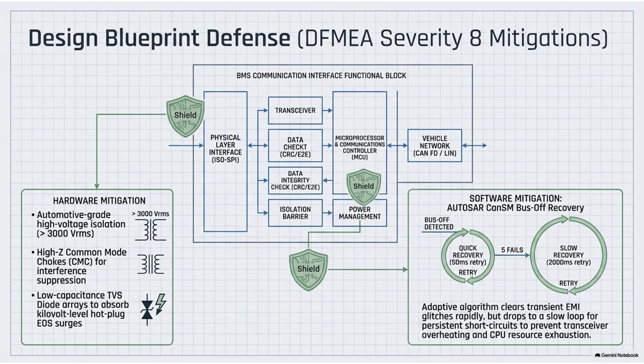What does that achieve? It utilizes the physics of electromagnetism to filter out the noise. Remember how the CAN bus uses differential signals? One wire goes positive, the other goes negative. Because the currents are flowing in opposite directions through the wires wrapped around the donut, the magnetic fields they generate completely cancel each other out. To the differential data signal, the choke is invisible. The data flows right through without slowing down.